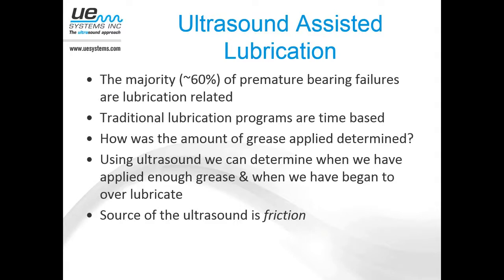And then taking it even a step further to some of the digital grease caddy instruments, we're able to actually track how much we put in and how much the PM called for, and the difference is the commodity savings on how much lube you didn't put into that bearing. And the side benefit is that if you'd put in how much the time-based PM said to put in, you would have over-lubricated it and probably failed the bearing. So these lubrication programs are something to take a real hard look at.